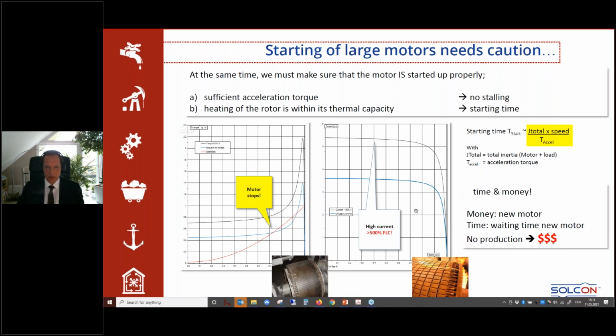What you also need to take into consideration is you need to take care of the starting time. It needs to be within reasonable limits. And starting time is proportional to the total inertia and to the speed, but also inversely proportional to the acceleration torque. So if the gap between the motor torque and the torque speed curve of the driven machine is too low, starting time is too long. And it's helping nobody if the calculated starting time is 2 minutes and the time speed curve of the motor says maximum 45 seconds. So also this has to be taken into consideration. You have to ensure a successful start.